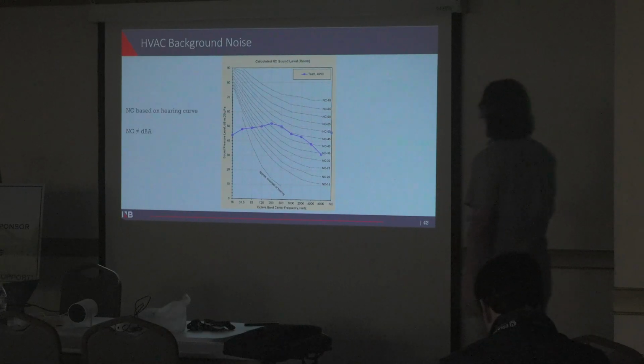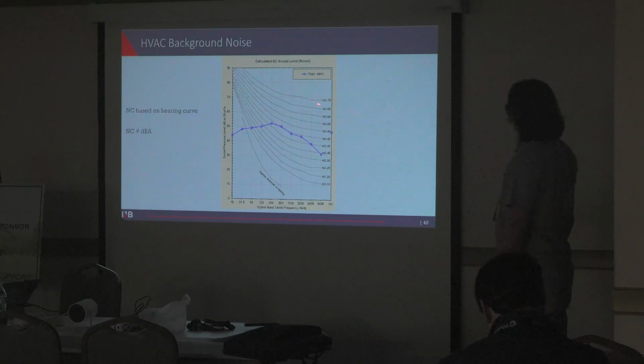Here's an NC curve and an NC table. These curves are similar to dBA, though not the same; there's no direct one-to-one conversion, you can't say 40 NC equals 40 or 45 dBA. But in general they track together, lowering one tends to lower the other. It's weighted somewhat like dB, which is why these curves are shaped as they are: at lower frequencies we don't hear as well, so we're less sensitive, while at higher frequencies we're more sensitive. The way we read this curve is simple: we just take the highest point.